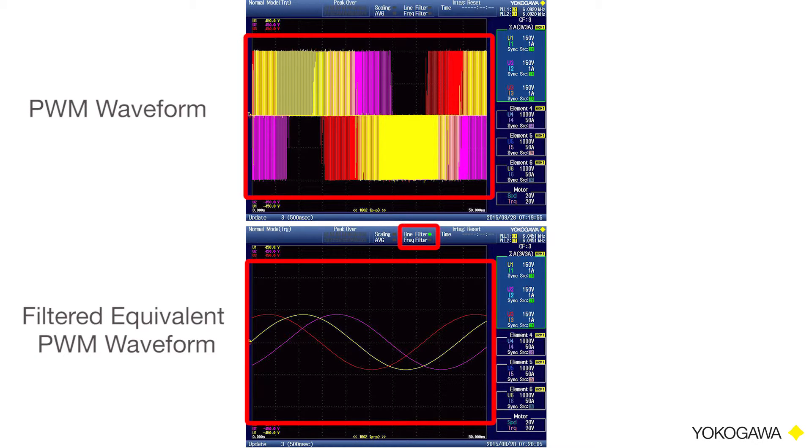With line filters turned on, you're not measuring the power contributed by the higher frequency components. Therefore, your overall efficiency measurements are better than they actually are.